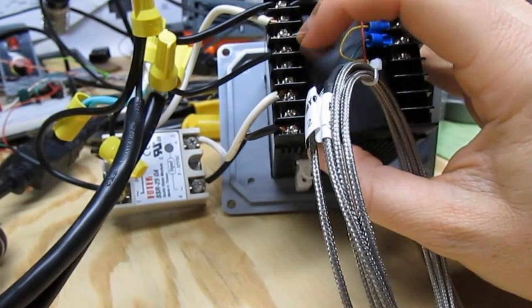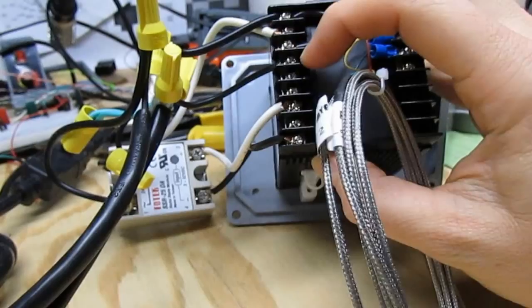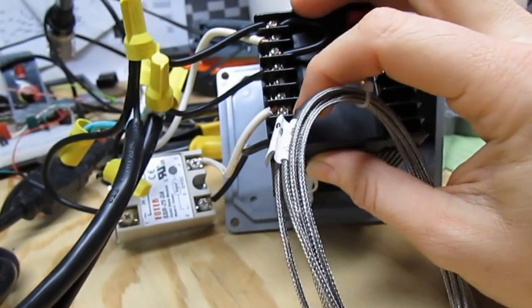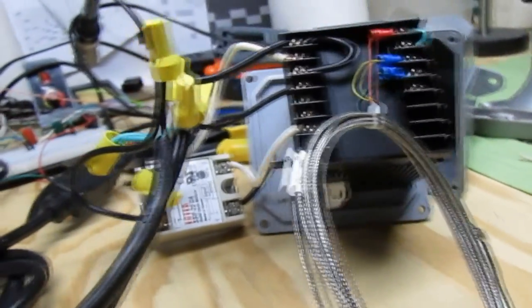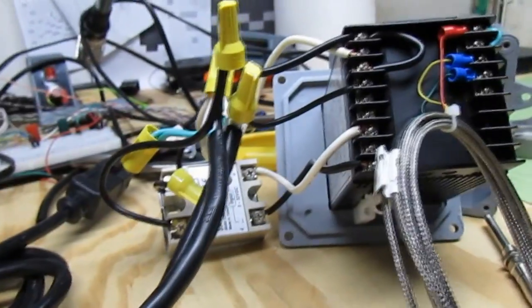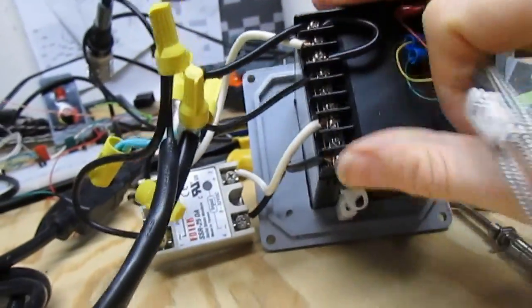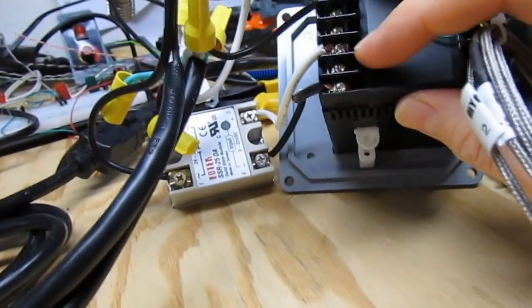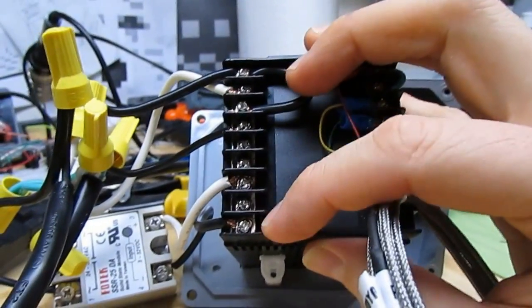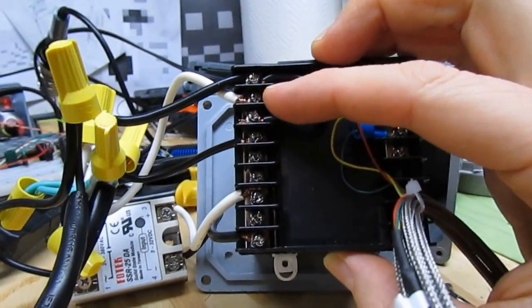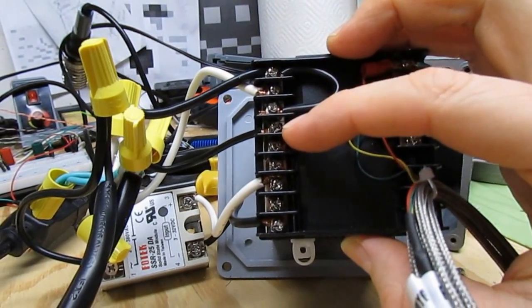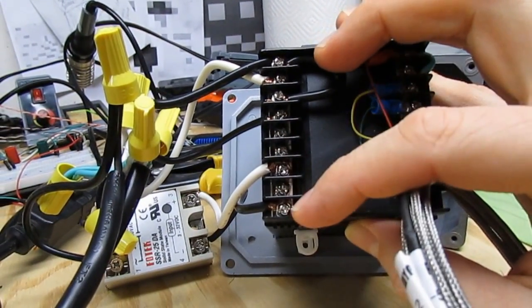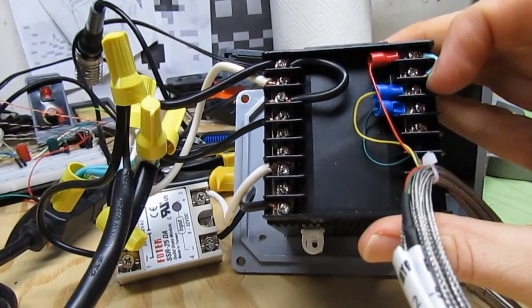Pin 3 and 4 are the alarm 1. And then down here, pin 7 and 9 are for the power of the SSR. Oops, sorry. So that's the output right there. So we have power input, we have alarm 1, we have output, those two, and then we have the sensor here to set up.